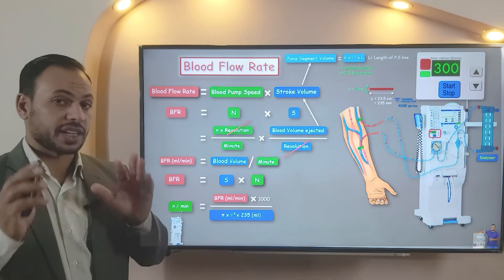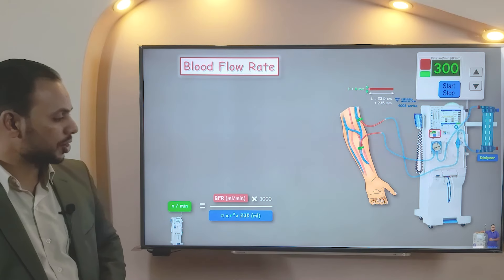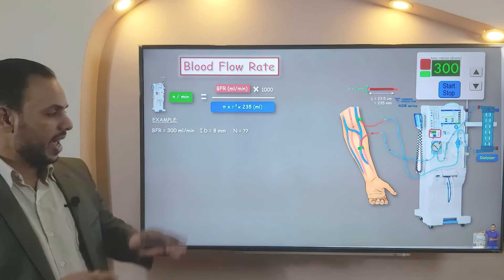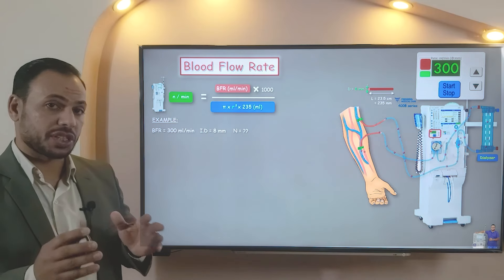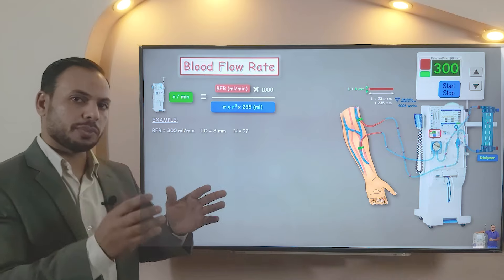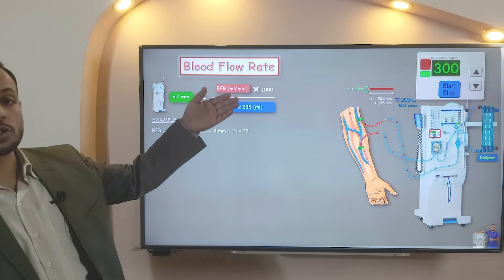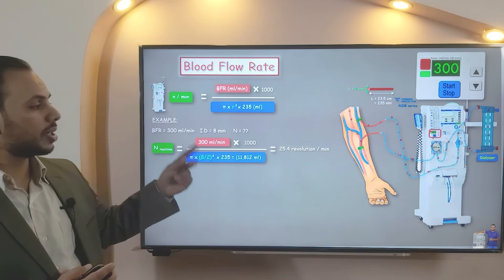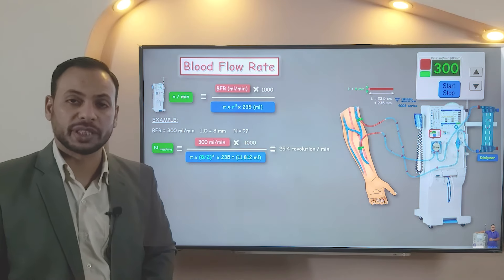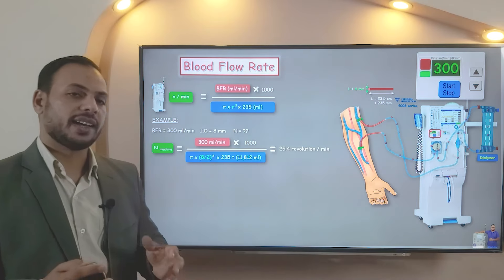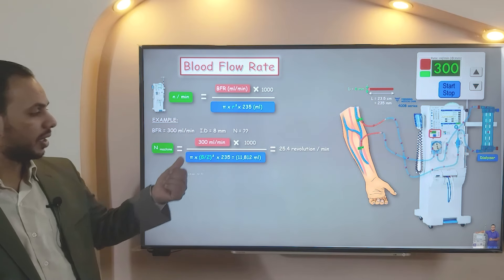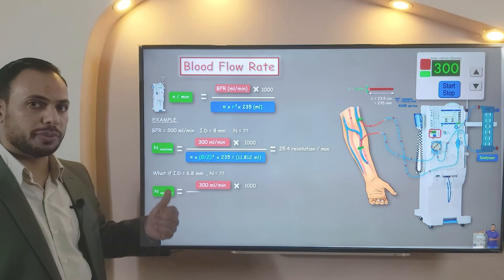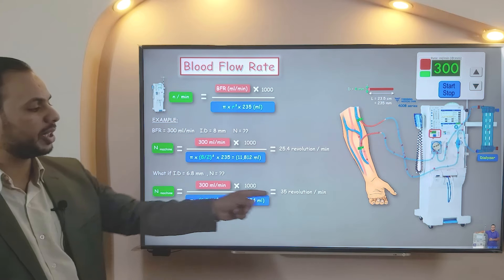Let's take an example to clarify the importance of this equation. Assume the required blood flow rate is 300 mL/min and the internal diameter of the actually used tubing set pump segment is 8 mm. By direct substitution in our equation, the number of revolutions per minute done by the machine will be 25.4 rev/min. If we change the blood lines manufacturer and have a new internal diameter of 6.8 mm, by the same method, the number of revolutions per minute will be 35.5 rev/min.